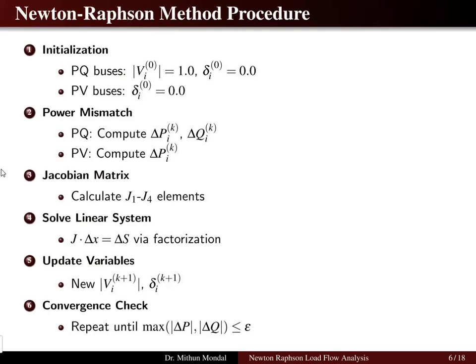In the Newton-Raphson method, the basic algorithm is: first, initialize the PQ bus voltage as 1 and angle as 0 (0th iteration), and the PV bus angle as 0. Second, compute the power mismatch — for the PQ bus, compute real and reactive power mismatch; for the PV bus, compute only real power. Third, calculate the Jacobian matrix elements J1 to J4 using the formulas from the previous slide.